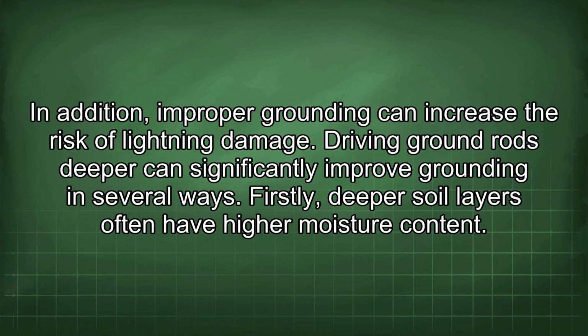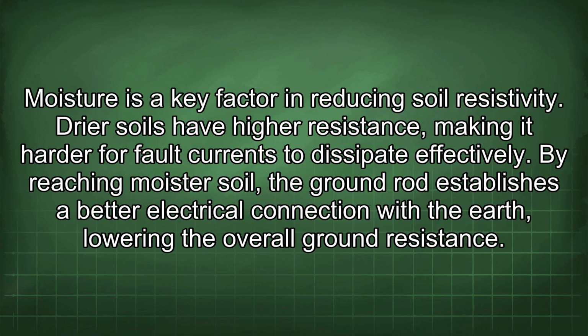Driving ground rods deeper can significantly improve grounding in several ways. Firstly, deeper soil layers often have higher moisture content. Moisture is a key factor in reducing soil resistivity. Drier soils have high resistance, making it harder for fault currents to dissipate effectively. By reaching moister soil, the ground rod establishes a better electrical connection with the earth, lowering the overall ground resistance.